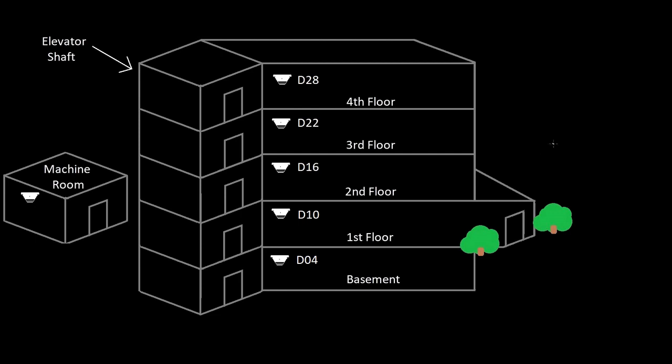There's a little bit more to elevator recall. Occasionally you'll have devices in the elevator shaft or in the elevator pit. We're going to ignore heat detectors for right now, but I will get into that in another video shortly. Then you'll always have one in the elevator machine room. What they want to have happen is if there's a fire somewhere in a location that would affect the elevator, like the machine room, pit, or shaft, they want the elevator, the fireman's hat - which is a little light located inside the elevator car - to start flashing.